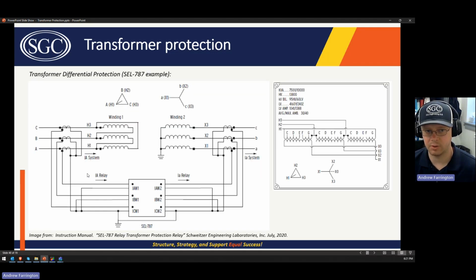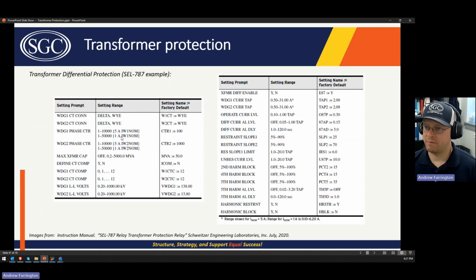You want to make sure that you're not limiting the thermal capabilities of the transformer with the CT ratio that you're connecting. And it depends on the utility. Some generally want it to be set lower so that you have a better accuracy, and some generally want the CT ratio to be set higher so that you can maximize the amount of loadability for the transformer in emergency situations. So the point with the setting is you just set the CT ratio to what the CT ratio is. So those are kind of self-evident.